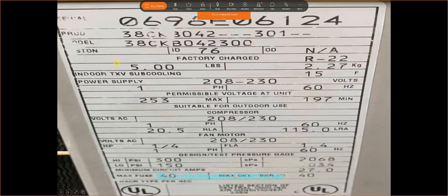With the Carrier Bryant units, even though the C and K are sort of fading out, I know that the model and product numbers are very similar. The 38CK is down here, so I can just copy all of this until we get to that 300 mark, where they have the dashes in the product number versus the model number. Piston size tells you what size piston you need. That's a type of metering device for the system. We're going to put that into the evaporator.